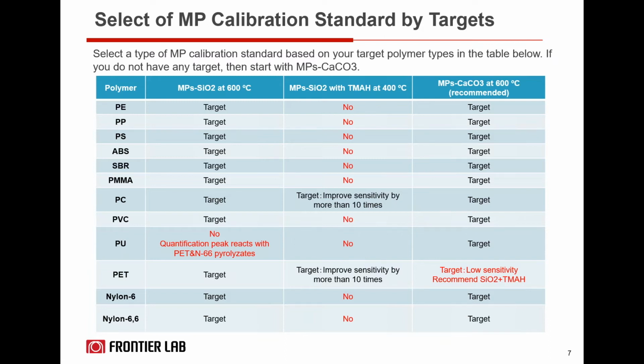So in that case, if you're going after PET and/or PC, polycarbonate, you can use MP's SiO2 with TMAH. TMAH is an alkali reagent, tetramethylammonium hydroxide. This is a reactive pyrolysis where you add this reagent into your sampling cup with your sample and then perform pyrolysis. The suggested temperature is 400 C. The other two, the MP's SiO2 and MP's CaCO3, are just flash pyrolysis simply at 600 C.